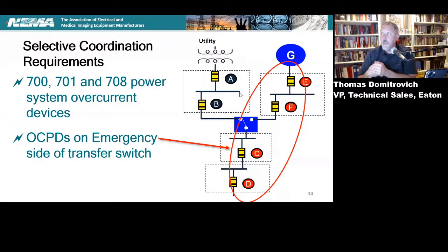Now, what you're seeing here is the discussion around what has to selectively coordinate. And what the 2020 version of the code did was basically put the debate to bed on whether or not devices A and B have to selectively coordinate with each other. Because the issue is, and you've probably gone through these debates, do I have to selectively coordinate A and B? They're not in the life safety system. They're not a part of the 700, 701, and 708. We've circled all of that stuff. They're outside of that. So there were public inputs put into panel 13 saying, hey, you need to mandate selective coordination on A and B.